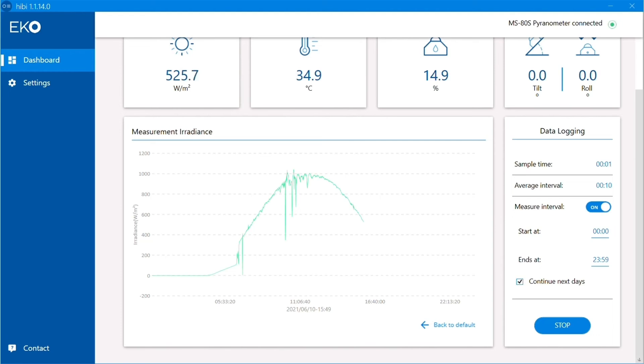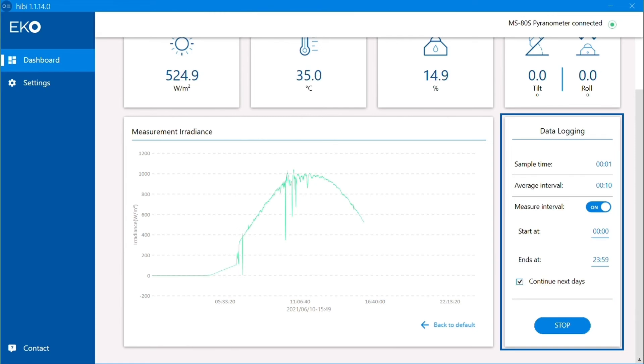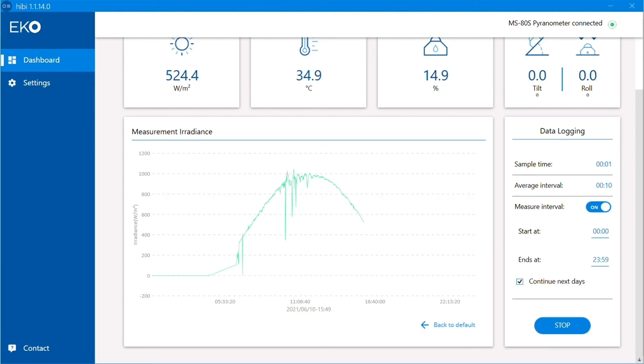Lastly, we have the Data Logging function. This allows you to save the measured data as a comma-separated CSV file directly to your PC. A continuous record with a specified time period may be set so that a new log file is automatically created each day, with the start date and time in the file name. This can supplement, or in some cases even replace, the need of a data logger or separate data collection device, so it's potentially cost-saving as well.